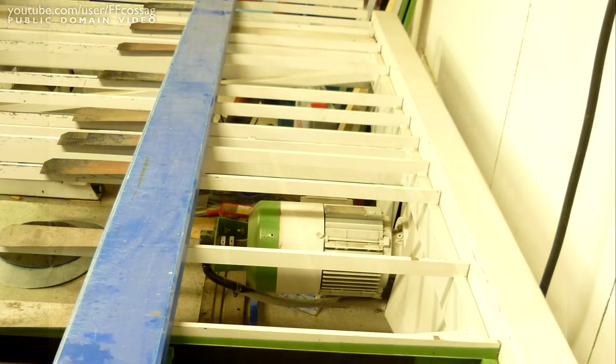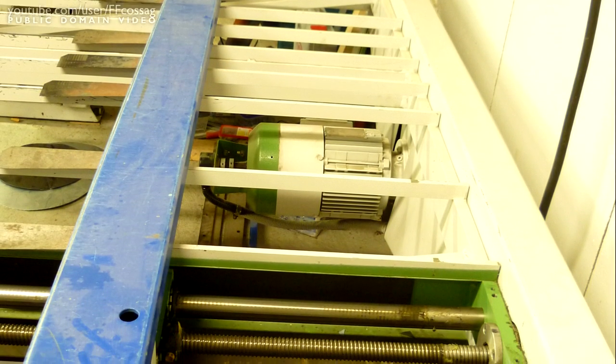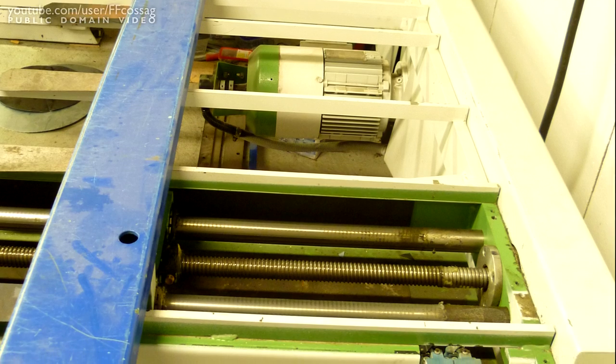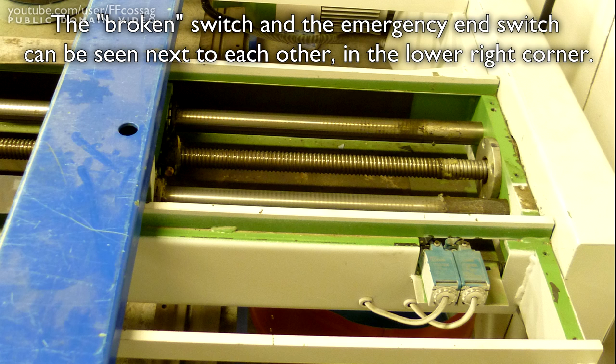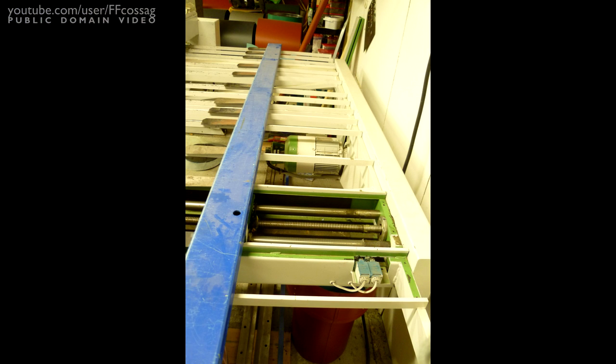We set to digging into the documentation, and I had a think, and I figured the machine probably has some way of figuring out where the position of that boom arm is, aside from just the switches. It has to know how far it's moved the arm. And if the counter for where the arm is isn't working, then it makes a lot of sense for the programming to ignore the limit switch. Because if the programming knows that the shaft isn't turning and the arm isn't moving, then it has no reason to consider the fact that the arm might be moving, because it knows it isn't.